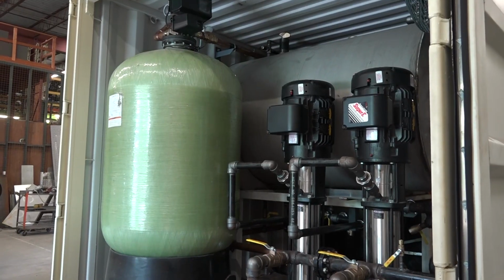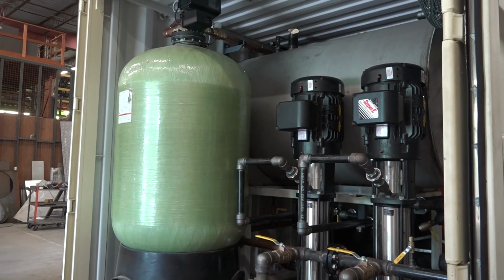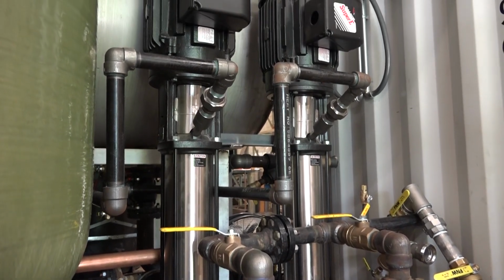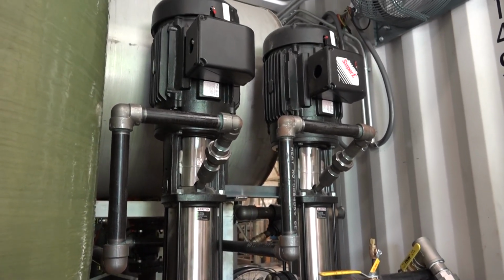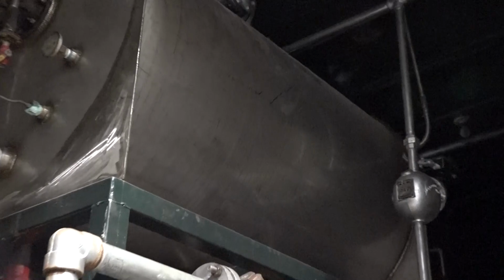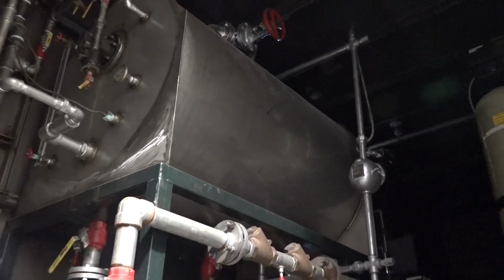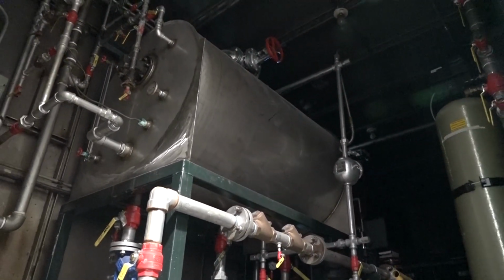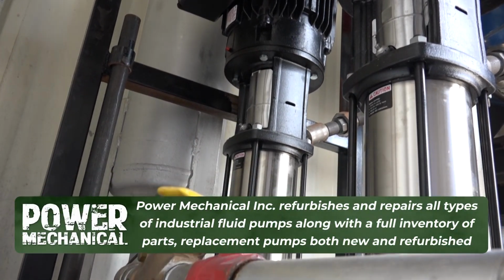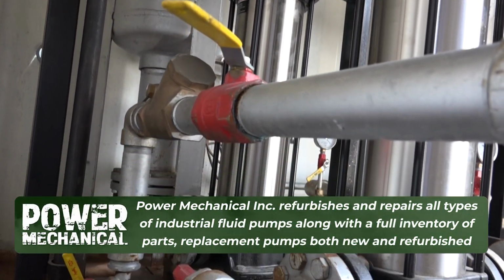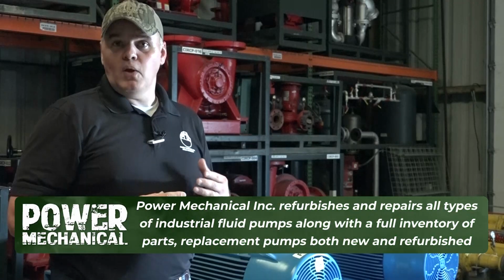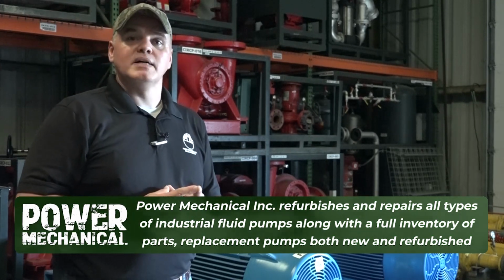Now, oftentimes, systems with high rates of condensate return can result in excessive feed water temperatures, which leads to this phenomenon of cavitation. Again, this typically can be remedied by providing the best possible NPSH to the pump to maintain as high of a pressure as possible, and the feed tank should be located well above the boiler whenever possible.